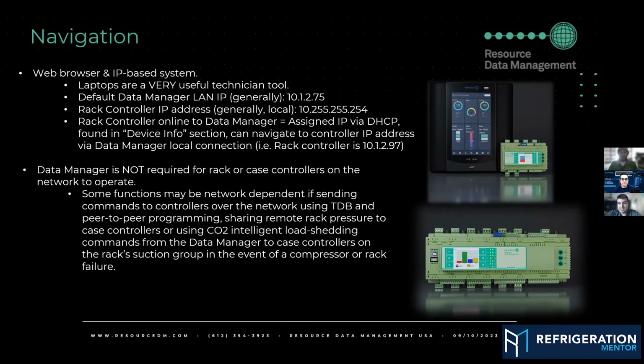The data manager is really easy to access. If you open the right side panel wing, there's 4 Ethernet ports there. You can plug into one of those on your laptop. The data manager then assigns your laptop an address, and the data manager IP address is 10.1.2.75 almost every time. You can change it, but I very rarely see it change. So that IP is going to be very useful. Or if you're going directly to a rack controller over like a printer cable or Ethernet, it's that 10.255.255.254 address that'll get you right into a rack controller.